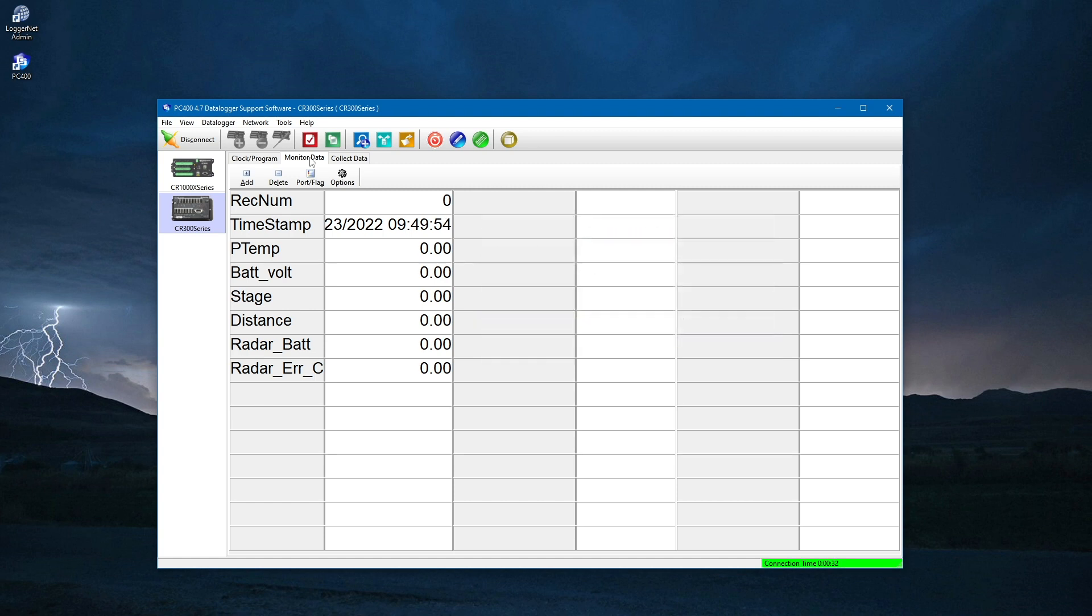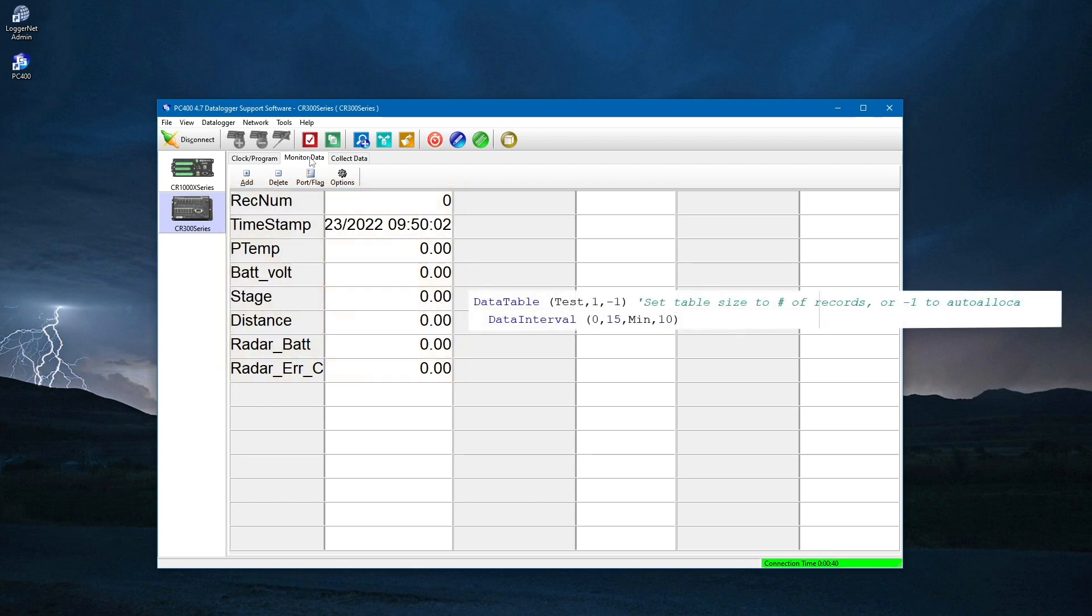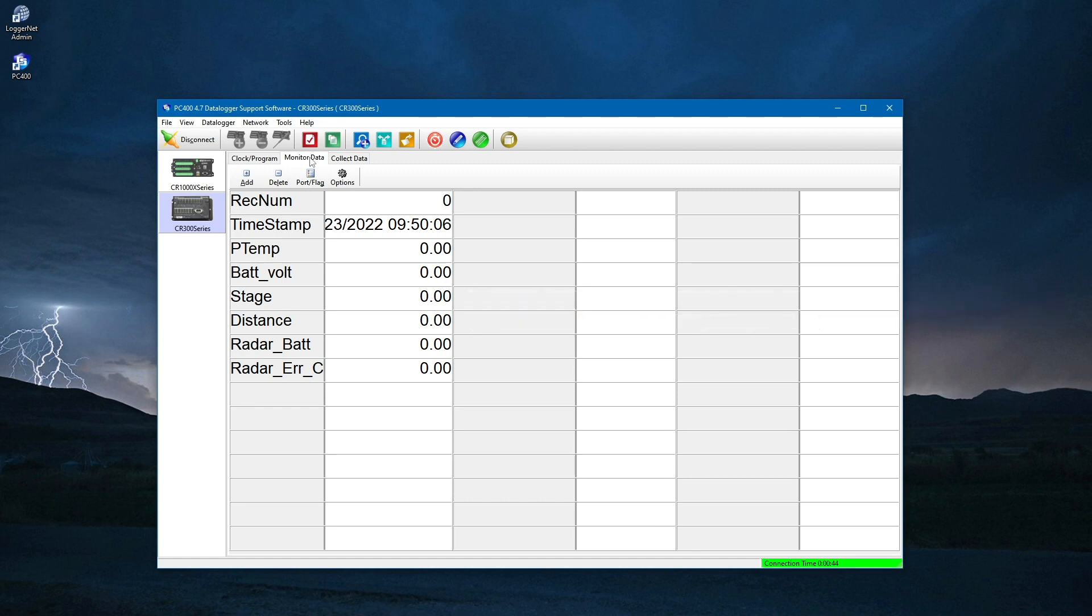I am satisfied with the order of the public variables, but I notice that the values associated with these variables are not updating. This is because the program is set up to measure and record data on a 15-minute interval. Most of the time, I will not want to wait 15 minutes to view data. So in the next video, I will show how to modify the program to make real-time measurements during a site visit, and then return to a 15-minute interval when I am done viewing the measurements.